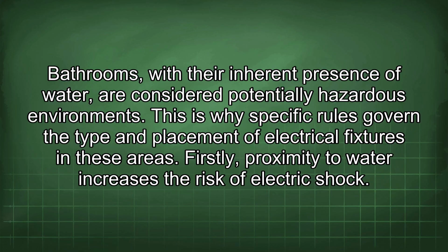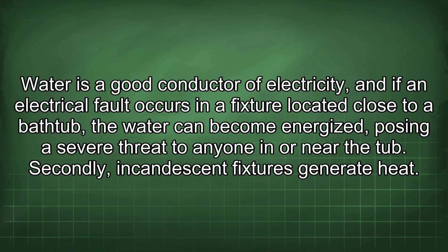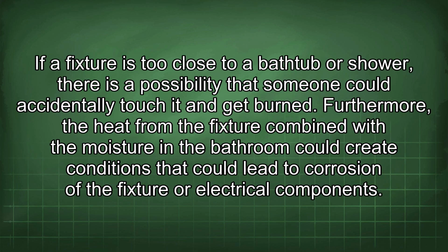Firstly, proximity to water increases the risk of electric shock. Water is a good conductor of electricity, and if an electrical fault occurs in a fixture located close to a bathtub, the water can become energized, posing a severe threat to anyone in or near the tub. Secondly, incandescent fixtures generate heat. If a fixture is too close to a bathtub or shower, there is a possibility that someone could accidentally touch it and get burned. Furthermore, the heat from the fixture combined with the moisture in the bathroom could create conditions that could lead to corrosion of the fixture or electrical components.